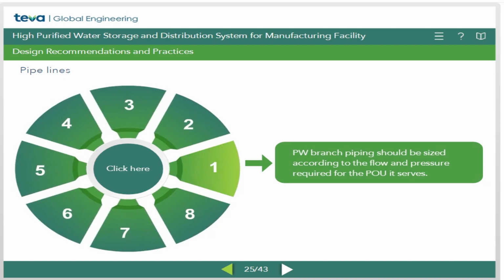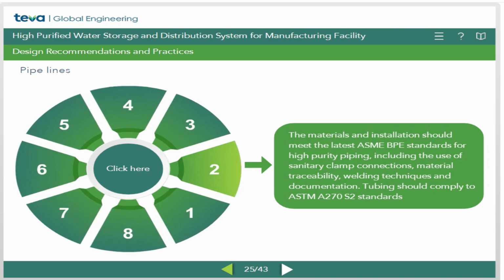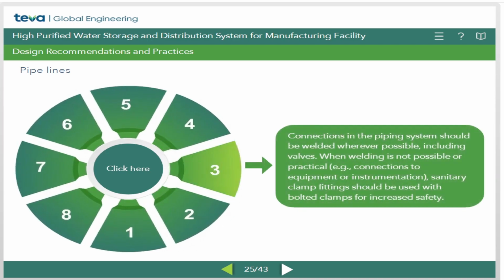Purified water branch piping should be sized according to the flow and pressure required for the point of use it serves. The materials and installation should meet the latest ASME BPE standards for high purity piping, including the use of sanitary clamp connections, material traceability, welding techniques, and documentation. Tubing should comply to ASTM A270 S2 standards. Connections in the piping system should be welded wherever possible, including valves. When welding is not possible or practical, sanitary clamp fittings should be used with bolted clamps for increased safety.